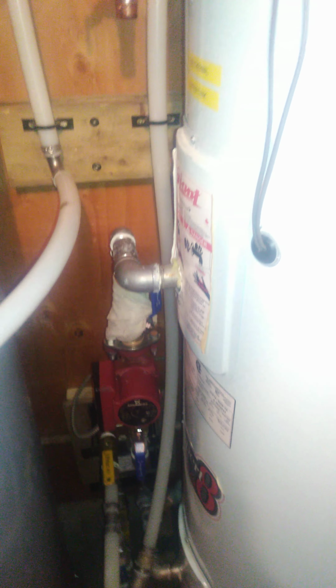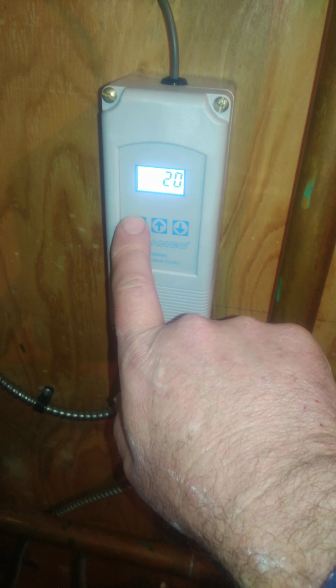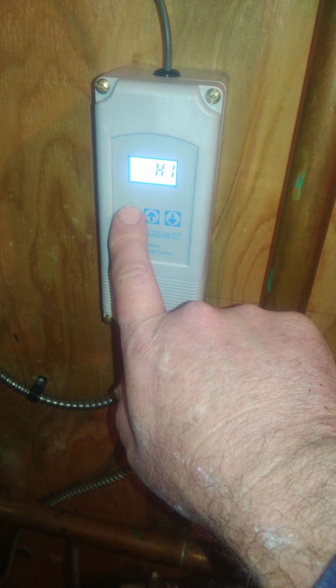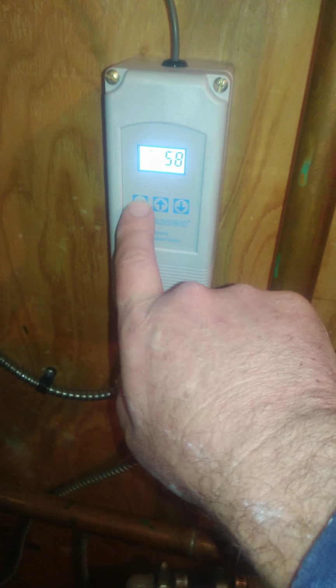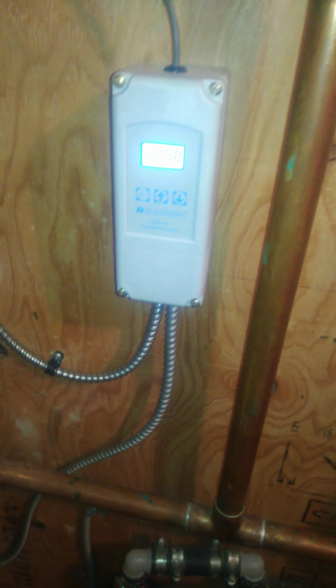I'm going to try to max out around that, that's why I set it at 130 here. I put a differential of 20, so it will come back on in high mode. Right now the water temperature is 58 because I haven't got anything running. With the differential set, at 110 degrees it'll kick back on, the pump will start circulating, and we'll be using the infloor throughout the house.